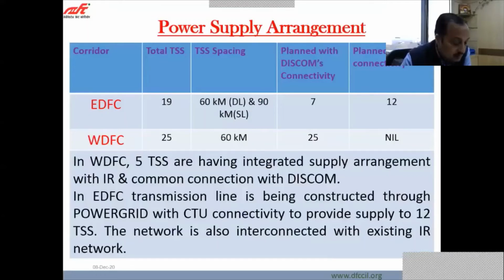Next is the power supply arrangement which has been adopted on EDFC and WDFC. In EDFC, there are a total of 19 substations with a spacing of around 60 km on double line and 90 km on single line. Seven substations have been planned with connectivity to the respective nearest discoms, and 12 substations with CTU connectivity. In WDFC, there are a total of 25 traction substations, at an approximate distance of around 60 km. And in WDFC, all substations have been planned with discoms directly, mainly on an open access basis.